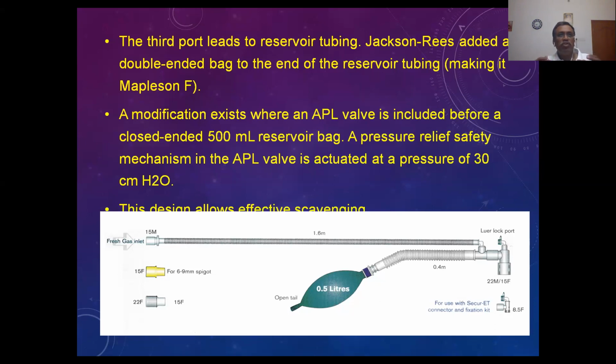So we cannot meet the patient's demand of peak inspiratory flow during inspiration, and whatever gases are present in the expiratory limb will also be sucked out, which is not adequate for the flow meter and the gases in the expiratory limb. So it will draw air from the atmosphere, leading to air dilution. Can you follow me? So air dilution will occur if the expiratory limb volume is less than the tidal volume of the patient. That is the most important point, because we cannot meet the peak inspiratory flow of 30 to 40 liters per minute. We have to remember it.